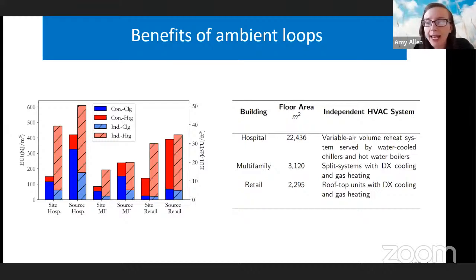And particularly in the case of the prototypical hospital building, the use of the ambient loop and electrified space heating systems resulted in a significant reduction in site energy use and also in a reduction in source EUI. And the electrification of heating contributes to the greater reduction in site EUI. And in this case, this was largely attributable to the fact that the prototypical hospital building had significant load diversity within its own zones, and thus its own water source heat pump loop, such as those that are used in buildings with independent systems, also allowed for a significant amount of load sharing, and thus a reduction in site energy use intensity relative to the independent systems.